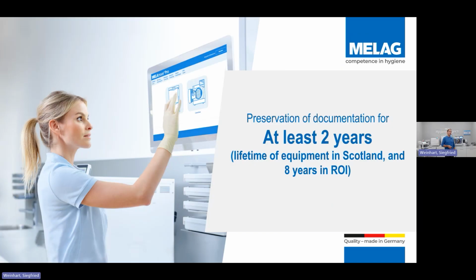So anything that we have within the UK, all of our logs from these, so our little test strips from our Helix devices, our cycle logs that are churned out of our sterilisers and our washer disinfectors every single cycle, every single day, must be kept for a minimum of 2 years within England and Wales. Within Scotland, they need to be kept for the lifetime of the equipment. Okay. The SHTM 01-05 came out last year, and it's slightly changed the lifetime of the equipment info. If you're in the Republic of Ireland, you're keeping that information for 8 years minimum as well. England, Wales, that time span of 2 years is likely to change at some point. It's just a matter of when.